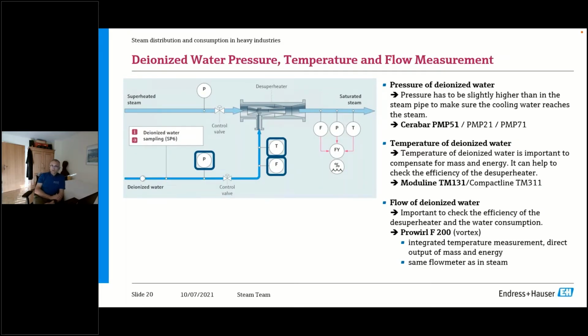When we talk about the deionized water, here we recommend to measure the pressure using our Cerabar, the PMP51, new generation 51B. Then for the temperature of deionized water, here you would use our Omnigrad TM131. And for the flow, you can use our Vortex meter, the Prowirl F200. You can even use that with an integrated temperature measurement at that point, or even with integrated temperature and pressure. This is also possible. So then you can actually output the energy of the feed water, of the deionized water you're sending to that device, for your energy calculation.